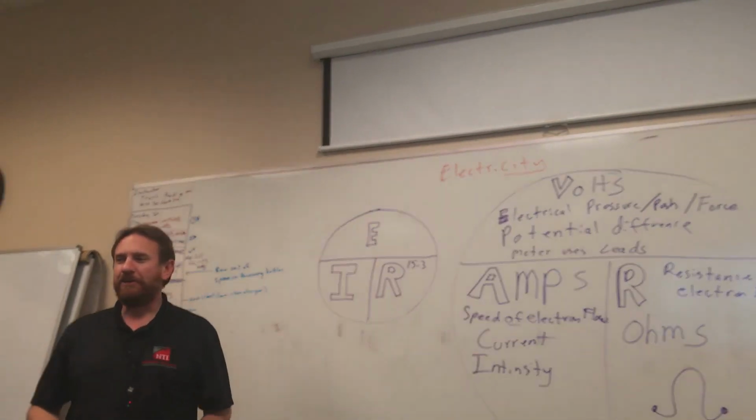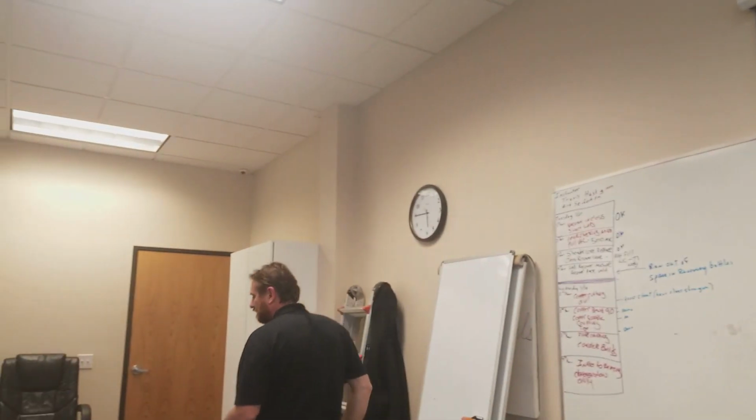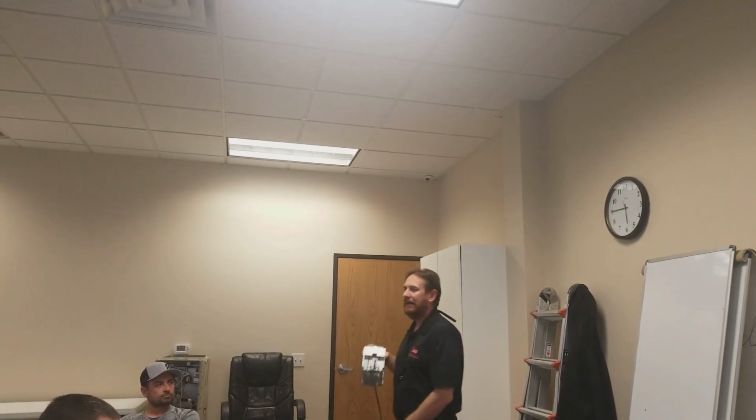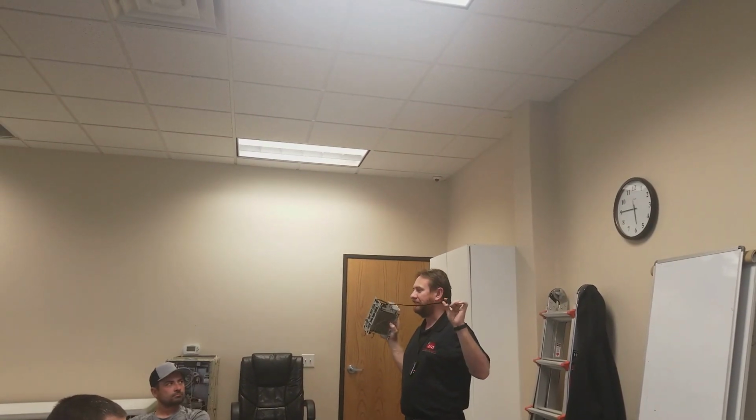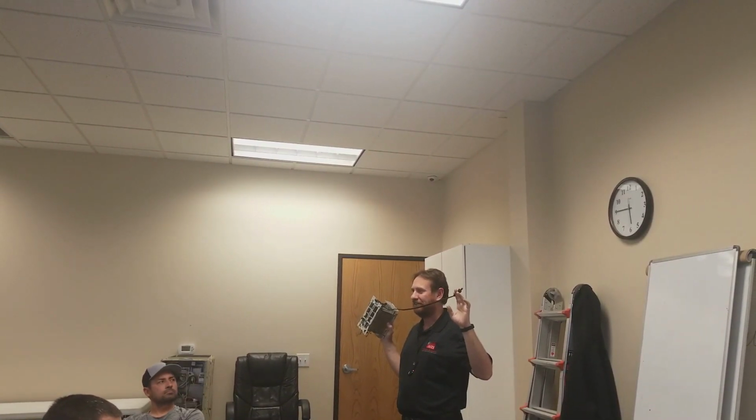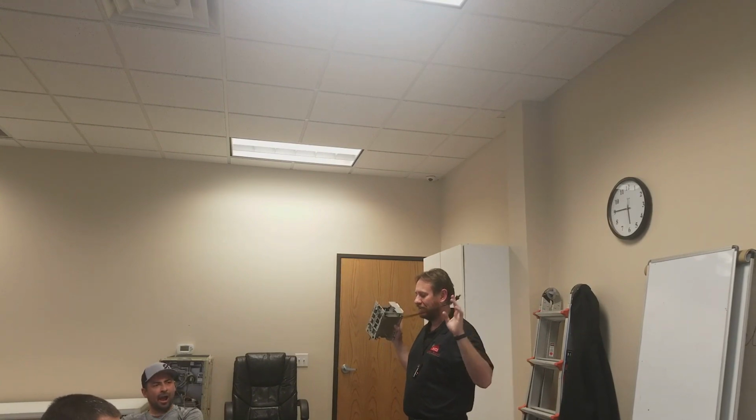15.3. If you're going to use ohms, whatever you're checking must be off and isolated. In other words, unplugged. Is this plugged in? No. Is it off? Yes. Is it isolated? I can use ohms.